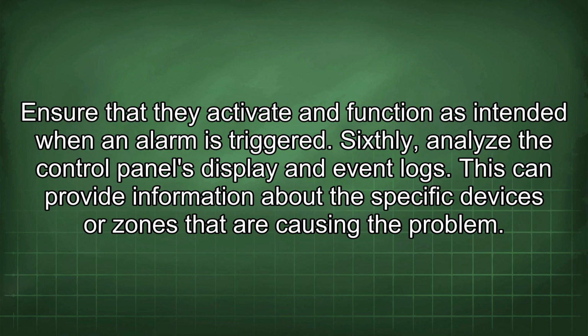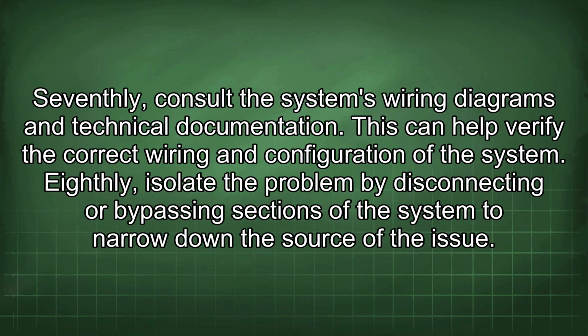Sixthly, analyze the control panel's display and event logs. This can provide information about the specific devices or zones that are causing the problem. Seventhly, consult the system's wiring diagrams and technical documentation. This can help verify the correct wiring and configuration of the system. Eighthly, isolate the problem by disconnecting or bypassing sections of the system to narrow down the source of the issue.